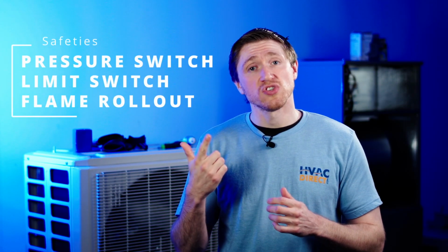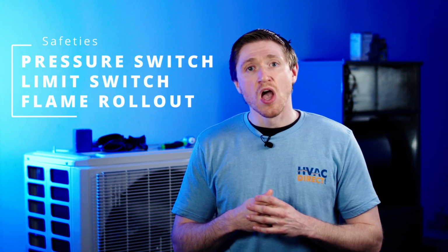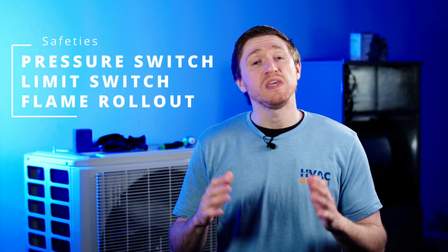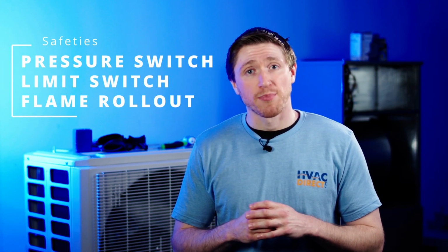If you don't see the inducer motor spinning, that's a problem, and that could be why the system is not operating. There are more checks that your service technician can do to make sure that the inducer motor is actually pulling enough negative pressure, but we would recommend leaving that to the professionals. After your inducer motor turns on, your furnace is going to check the safeties. There's three main safeties that the furnace is going to check: a pressure switch, a limit switch, and a flame rollout switch. All three of these safeties must be closed in order for the furnace to operate.